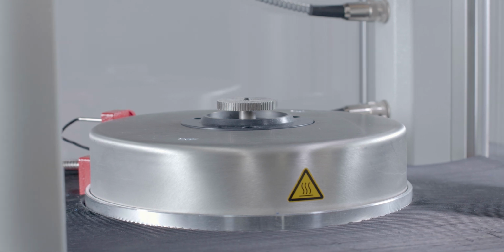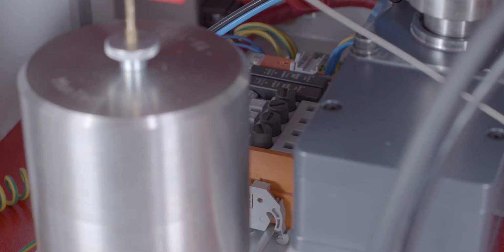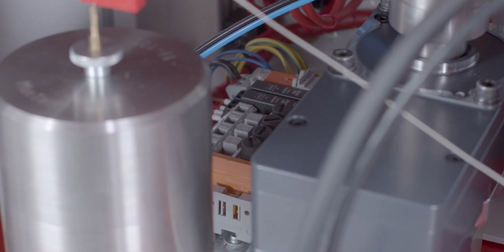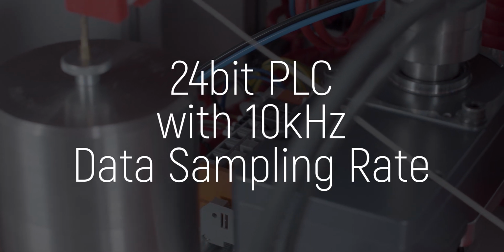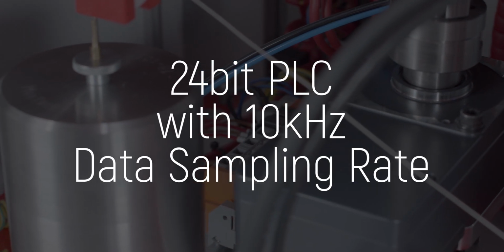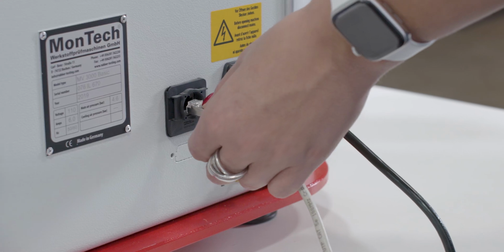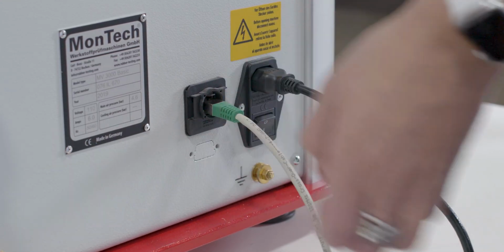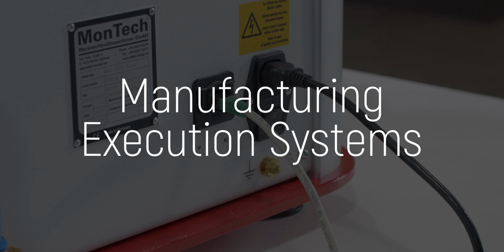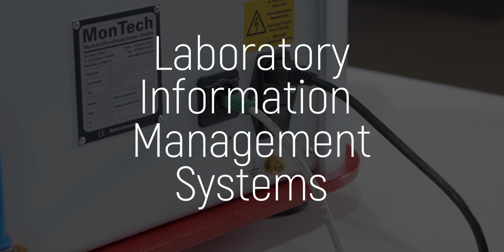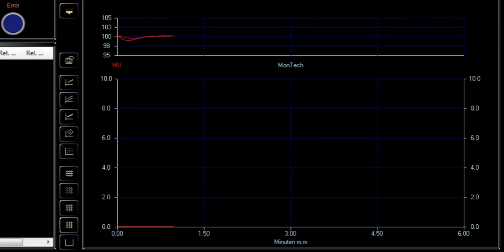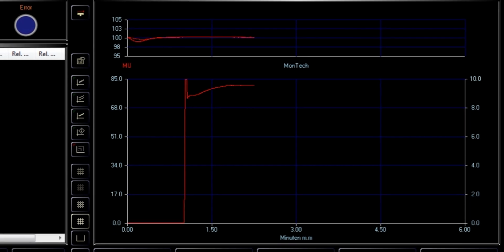To process and analyze the highly complex data streams from testing, the MV3000 Basic uses a 24-bit PLC with 10 kHz high-speed data sampling rate. It also features Ethernet connectivity for the fastest data output to networks, manufacturing execution systems, and laboratory information management systems. Data from the test is displayed live in the software as the test is performed.